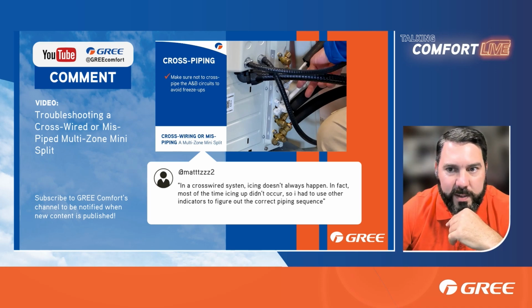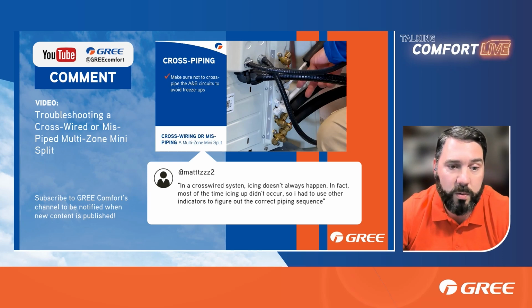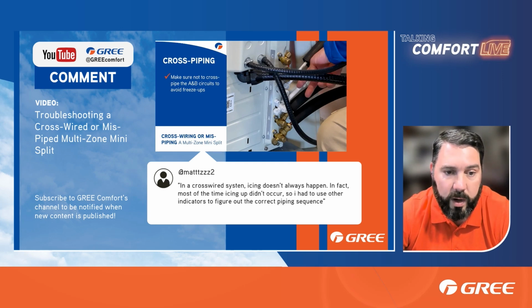And that's the test. Like if you were to call tech support, that's what we would tell you to do. Turn all of them off, turn one on in cool mode, and then see if that one actually cools. If it does not actually cool, then go look for the one that's starting to frost. Which coil is cold? That's how you'll find your crossed wiring.